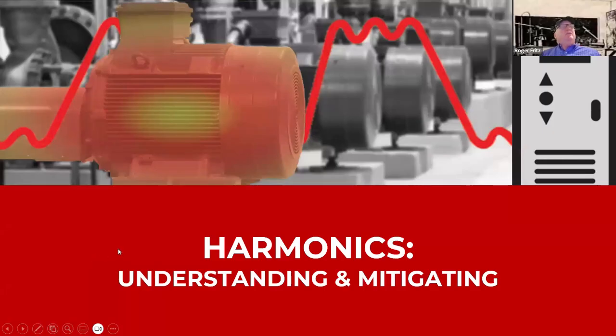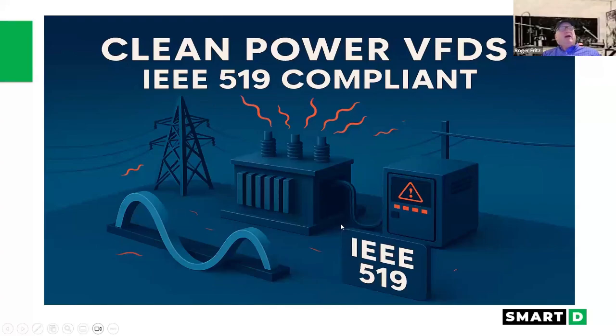So that's where I want to talk about what's been done for quite some time, about harmonics and the understanding of the mitigation that's out there, meaning the ways to get rid of it. So there is a compliance requirement, and I know a lot of power companies are becoming more and more involved in this on clean power VFDs. And you're supposed to be IEEE 519 compliant, but they've kind of overlooked it because also the units that they're putting out from solar are inverters, basically creating sine waves to put back on the grid. So they're masking the problem.